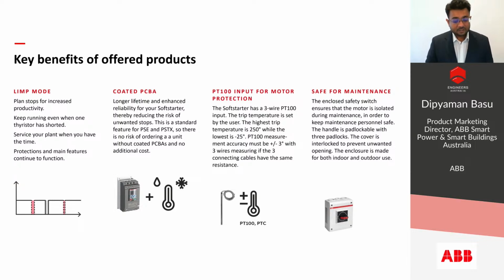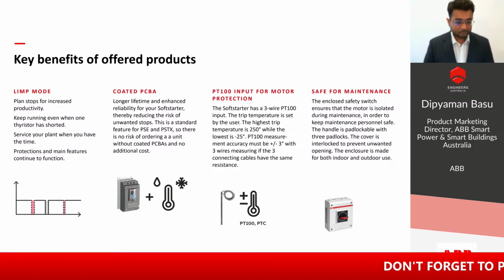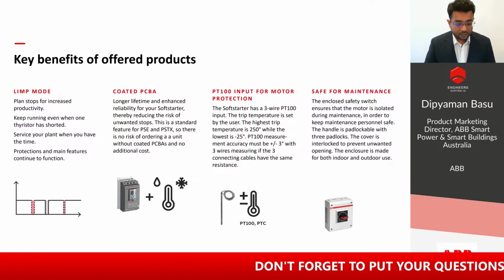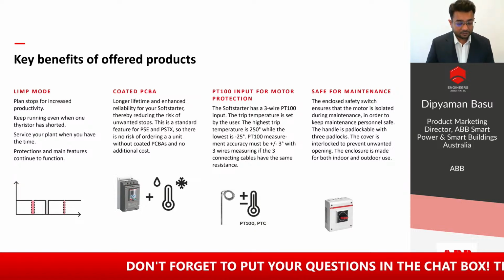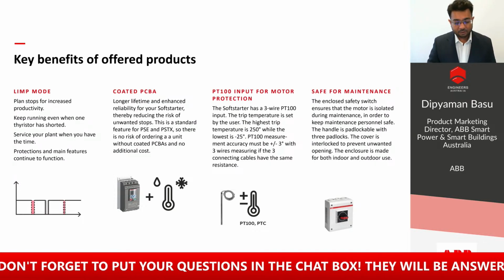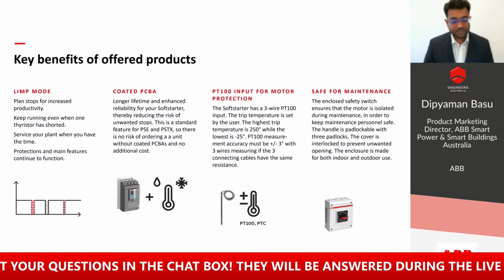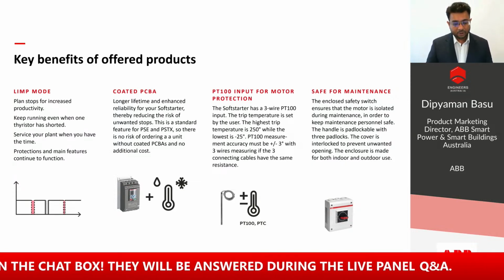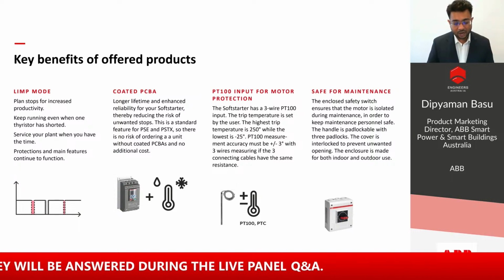When we look at some of the other specific features of our soft starter ranges, we have limp mode. Limp mode is an interesting feature that allows us to continue to run the pump or the motor which the soft starter is feeding, even if one of the thyristors has shorted and is not working. This allows continuity of operation and the ability to plan repairs and schedule maintenance. With the soft starters, it's a standard feature to have a coated PCBA card, again allowing lower risk of stoppages and issues within that particular installation, but also allowing reliability of the installation in harsher climates.